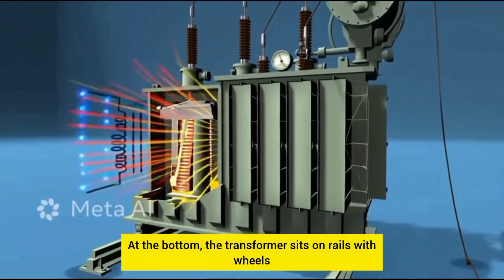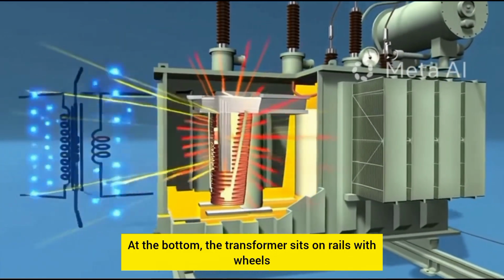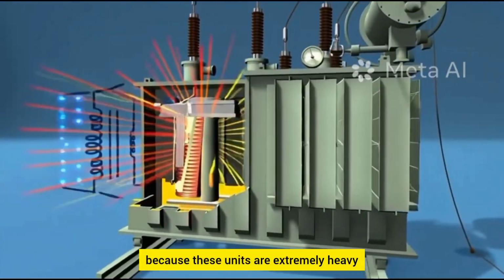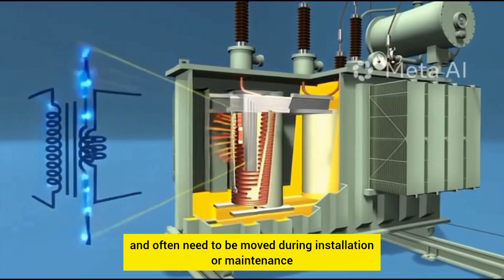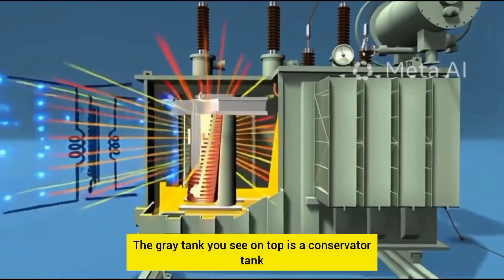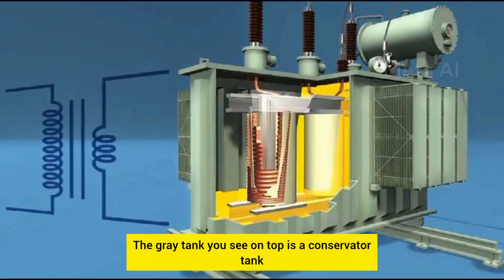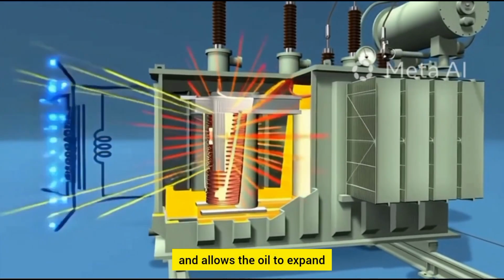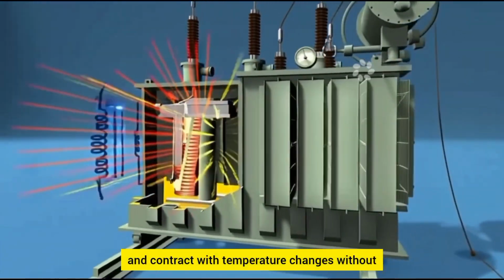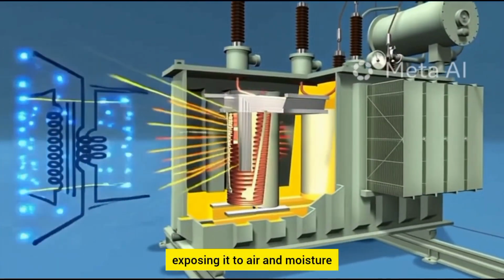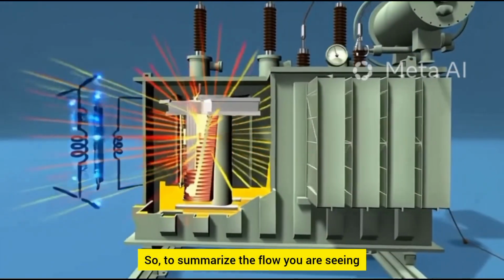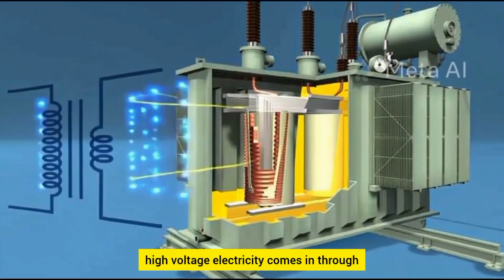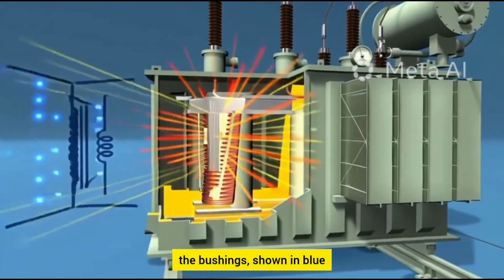normal. At the bottom, the transformer sits on rails with wheels because these units are extremely heavy and often need to be moved during installation or maintenance. The gray tank you see on top is a conservator tank. It holds extra oil and allows the oil to expand and contract with temperature changes without exposing it to air and moisture. So, to summarize the flow you are seeing, high-voltage electricity comes in through the bushings, shown in blue.